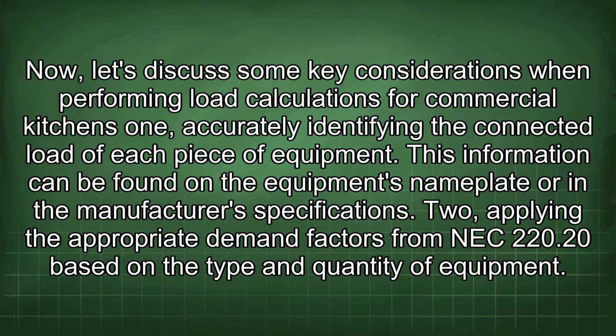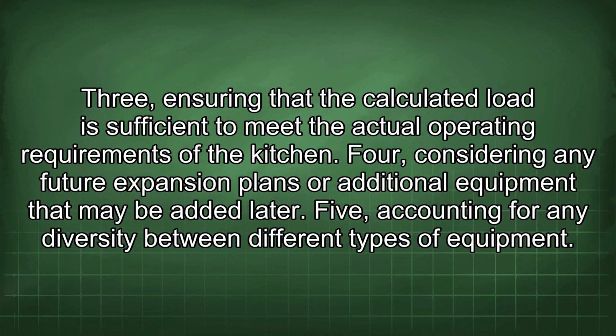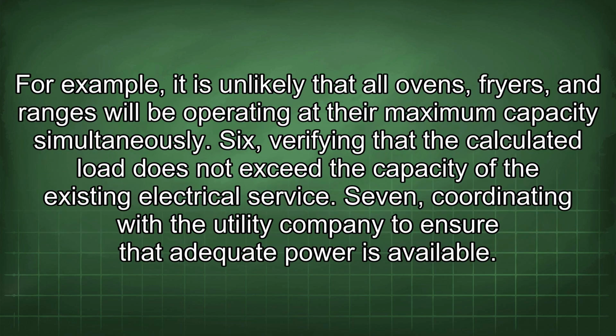1. Accurately identifying the connected load of each piece of equipment. This information can be found on the equipment's nameplate or in the manufacturer's specifications. 2. Applying the appropriate demand factors from NEC 220.20 based on the type and quantity of equipment. 3. Ensuring that the calculated load is sufficient to meet the actual operating requirements of the kitchen. 4. Considering any future expansion plans or additional equipment that may be added later. 5. Accounting for any diversity between different types of equipment. For example, it is unlikely that all ovens, fryers, and ranges will be operating at their maximum capacity simultaneously.